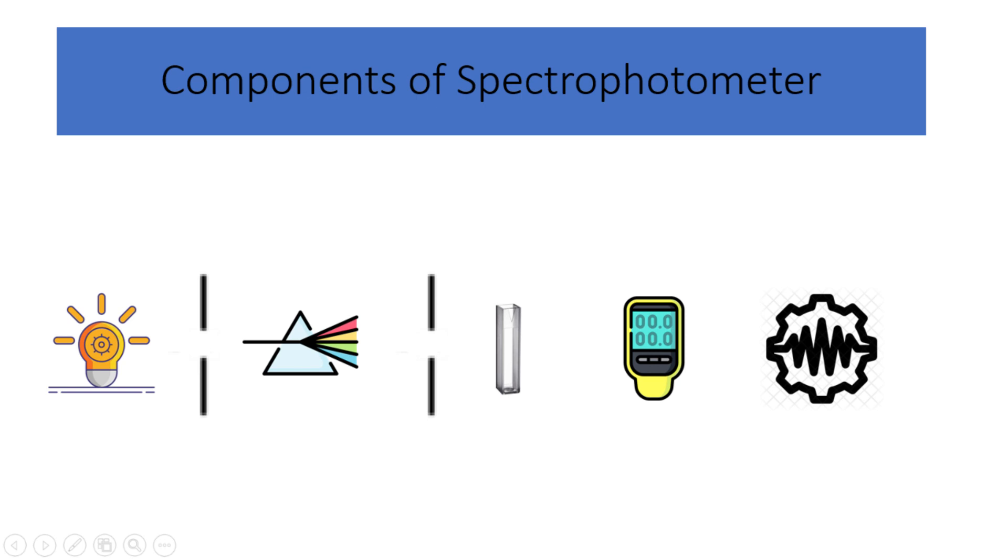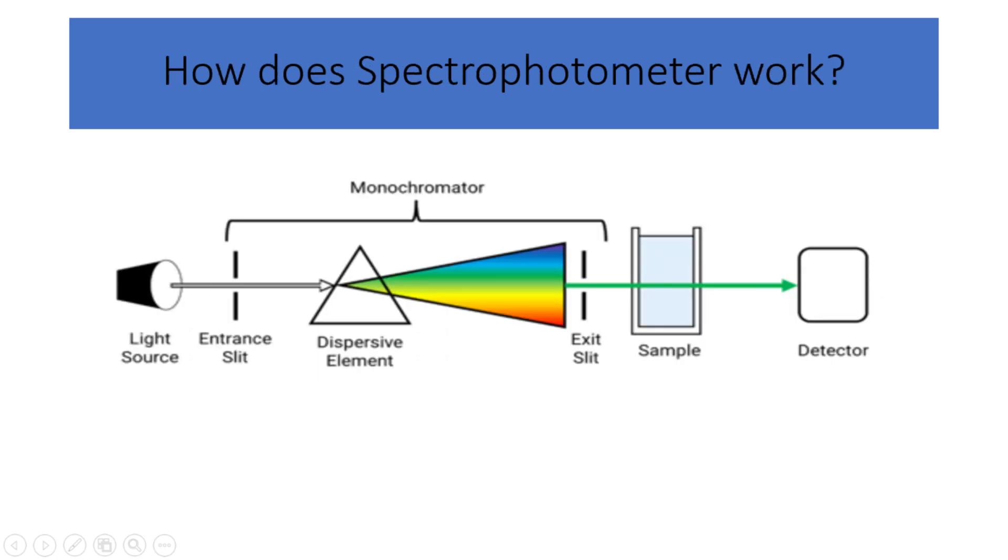How does spectroscopy work? Light from the source passes through the entrance slit and enters the monochromator. The monochromator disperses the light into its different wavelengths using a prism or grating. The dispersed light beam is directed toward the sample compartment, where the sample is placed. The sample interacts with the light, causing absorption or scattering of specific wavelengths based on its composition and properties.